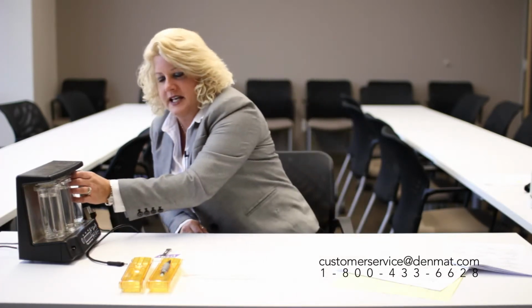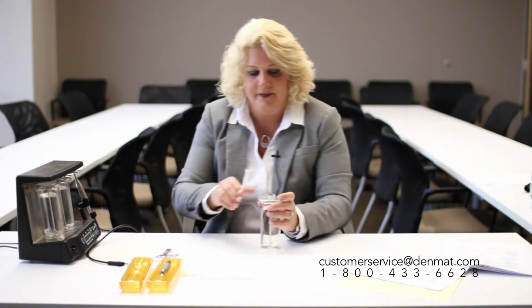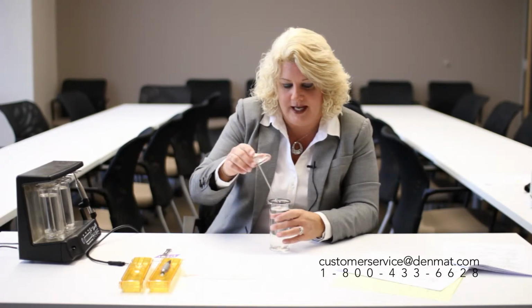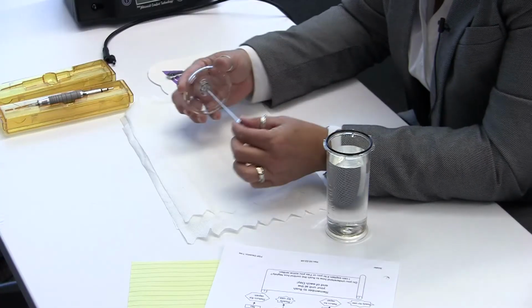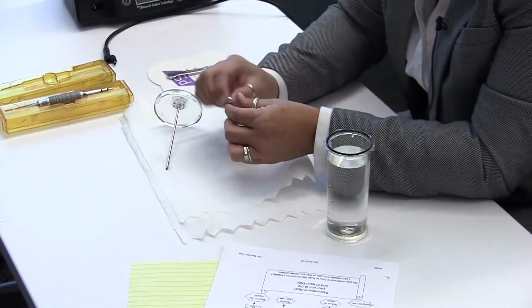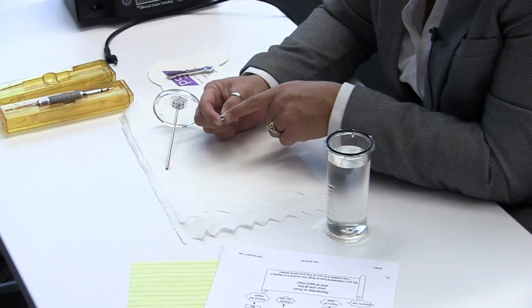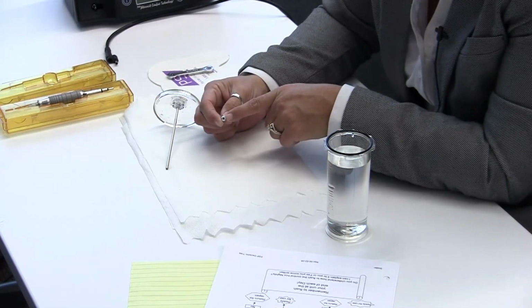But let's take a look at what we find out if the bottle is clogged. One of the ways that we can do that is by shutting the unit off and then taking one of these bottles out. There are some areas that I'm going to ask you to look at. So we're now going to take out this stem or the lid to the bottle, and we're going to be able to take off this piece down here at the bottom. And down here at the bottom, there is a screen that looks just like the screen on your kitchen faucet. We will ask you to look at it and also use your air syringe to clean this area out and blow some air through it. Sometimes medication can be crystallized at the bottom, and that's what's preventing it from coming out.